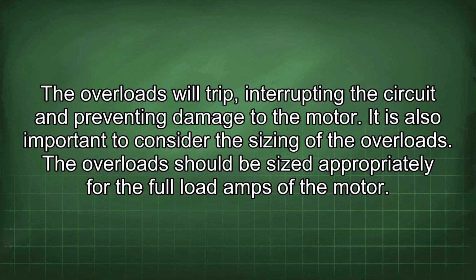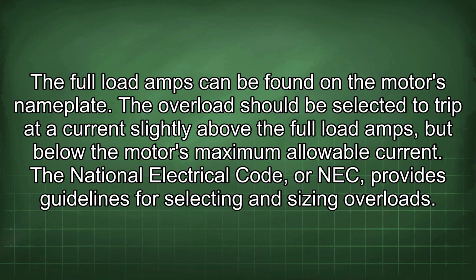It is also important to consider the sizing of the overloads. The overload should be sized appropriately for the full load amps of the motor. The full load amps can be found on the motor's nameplate. The overload should be selected to trip at a current slightly above the full load amps, but below the motor's maximum allowable current. The National Electrical Code, or NEC, provides guidelines for selecting and sizing overloads.